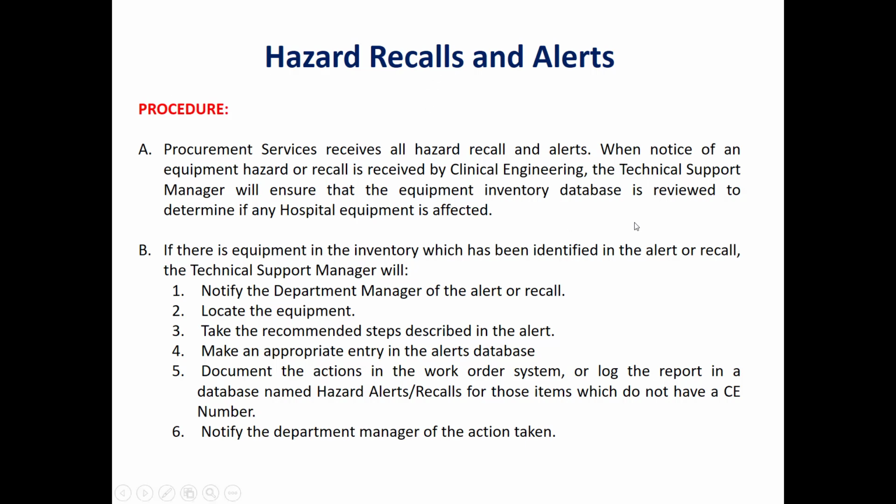Then the manager or director of the clinical engineering department will ensure that the equipment inventory database is reviewed to determine if any hospital equipment will be affected by this recall or alert.